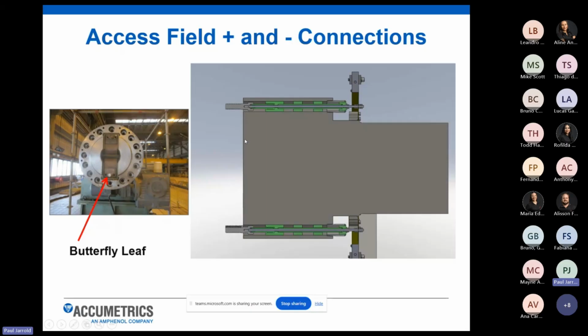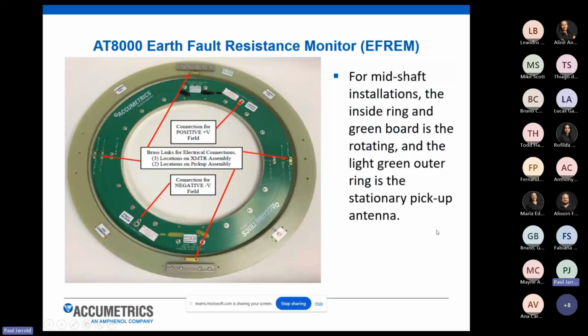So this gets mated together, and that's how they make an electrical connection between the exciter and the generator rotor. So we have to gain direct access to these field windings, and we do that by routing a threaded rod down through the bore of the coupling flange, and it gets screwed into the bolts that hold the electrical connection between the generator rotor and the brushless exciter rotor. Once that is done, we put some insulation pieces inside the coupling bore, and then we're ready to connect our rotating transmitter, which is this image here on the right. And we'll go into a bit more detail on what that looks like.